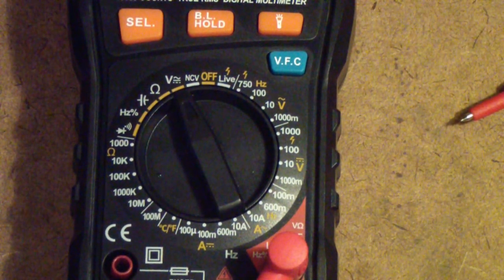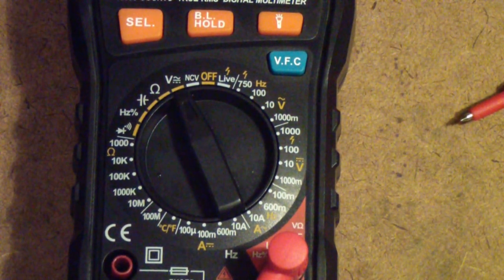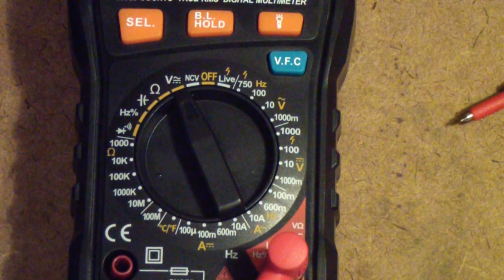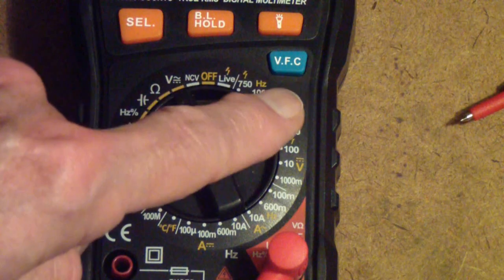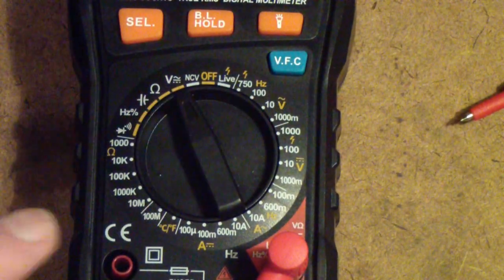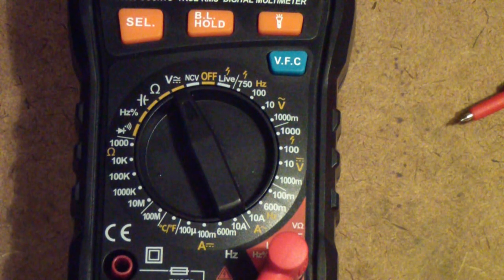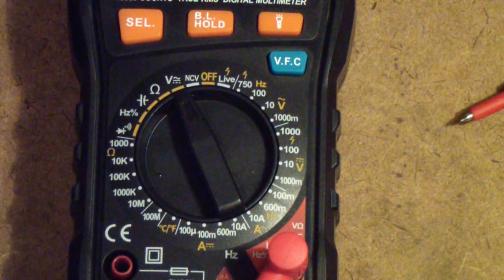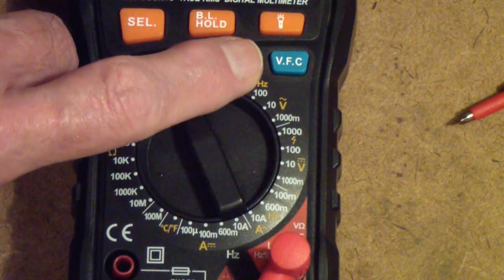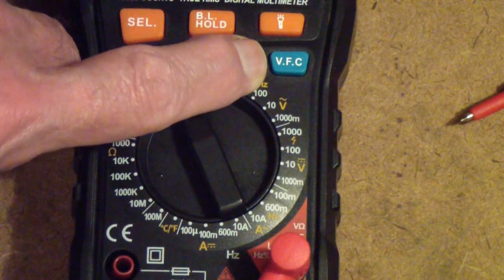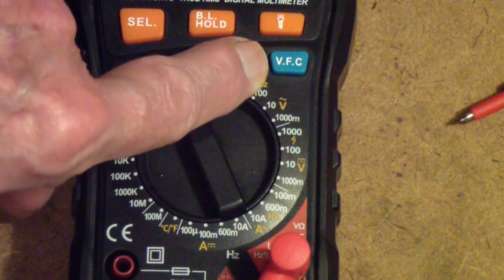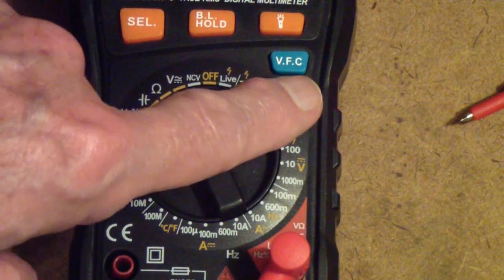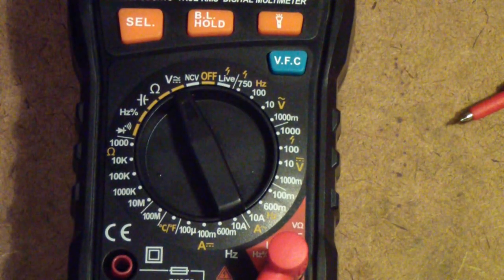But if you try to use a conventional meter to measure on the motor side of those controllers, you'll get erroneous readings. Fluke in their model 87—maybe in some others but the first time I saw it was in the Fluke 87—introduced a low-pass filter that you could engage in the AC mode.